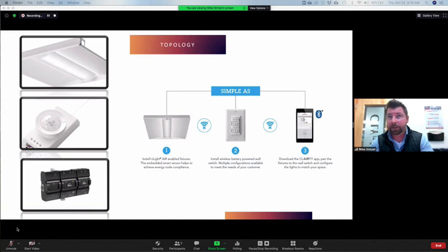In an LLLC system, everything is addressable. Typically in an addressable system, you can change the addresses and all that kind of stuff. With these, the addresses are pretty much set out of the factory. You can see what that address is as you get into the commissioning, but you can't typically change what that address is because it's set by the manufacturer and it has to communicate back to a head end. Whereas like a DMX system or a DALI system, I can change addresses on whim.